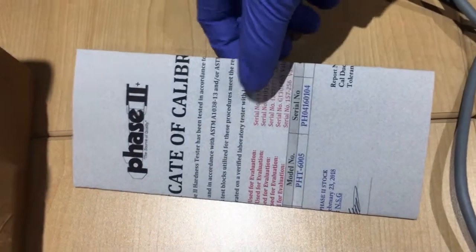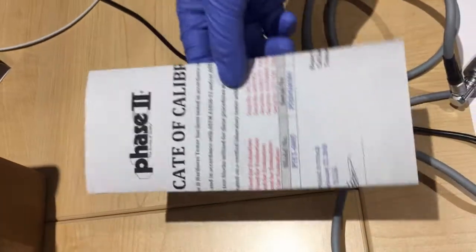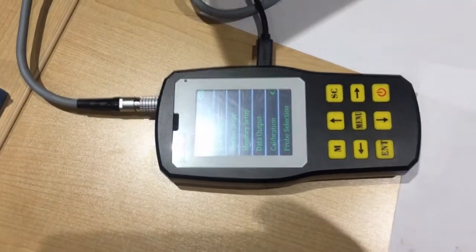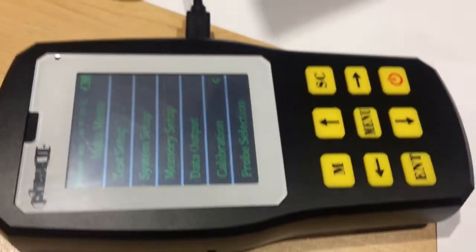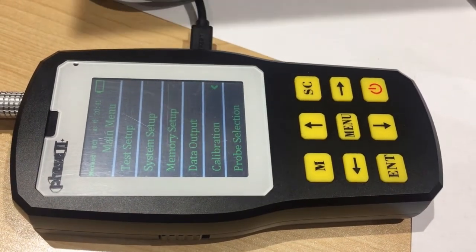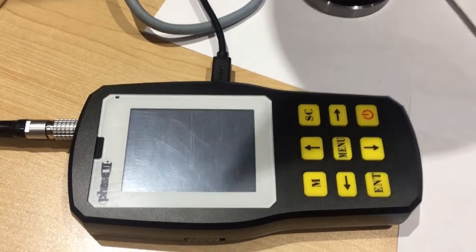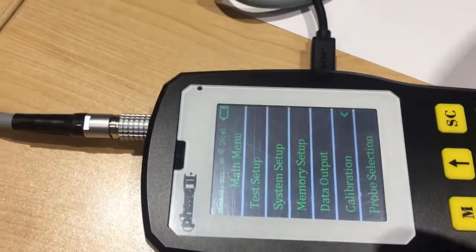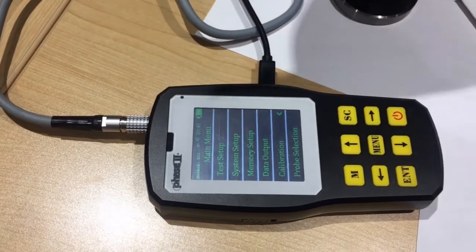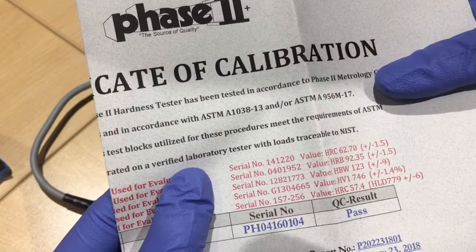Here is the calibration. For calibration, there is a certificate certified by Phase II Plus, and it comes out with your instruction manual. Here it is. As shown in our case, this machine is calibrated at February 23rd, 2018. And in accordance with ASTM A1038-13 and ASTM A956M17, which shows here. That's what the factory set up for us.